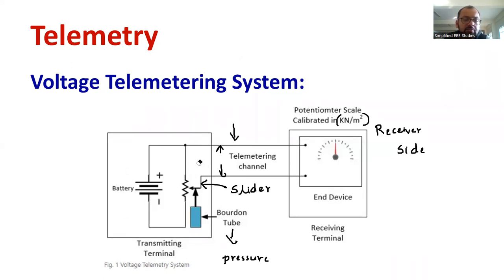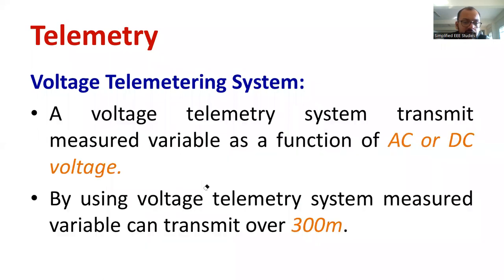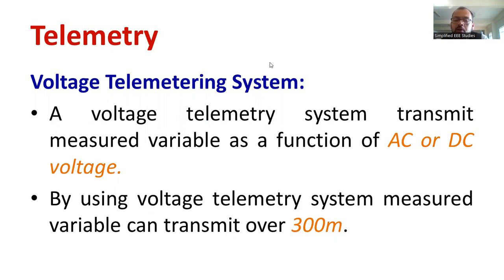For your better understanding, I have made a PPT. Let me show you what I have written. As you can observe the slide, I have mentioned the details of the voltage telemetry system. It can be used as AC or DC voltage — there is no issue. The distance is restricted up to 300 meters. If you want to go beyond 300 meters, you need to use a different type of system other than landline telemetry.